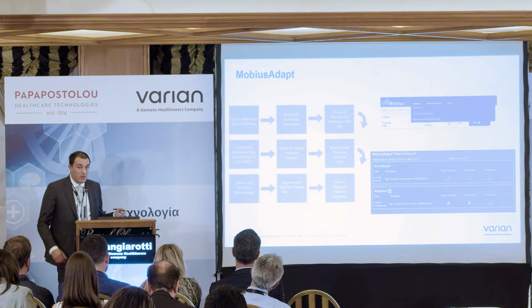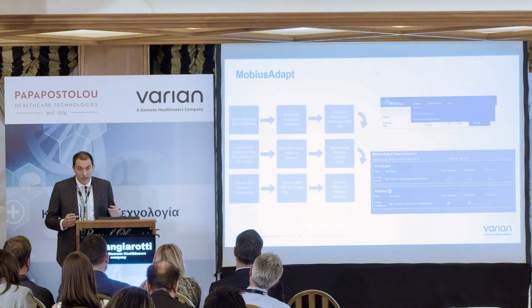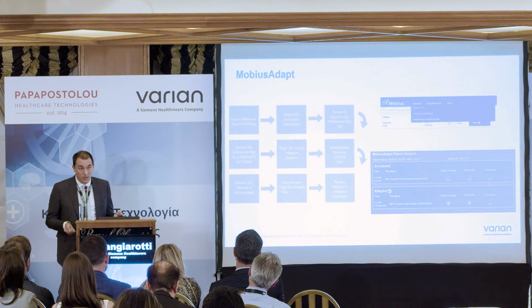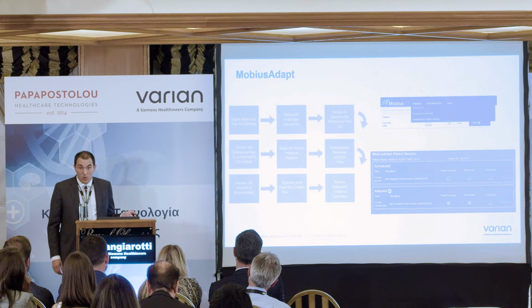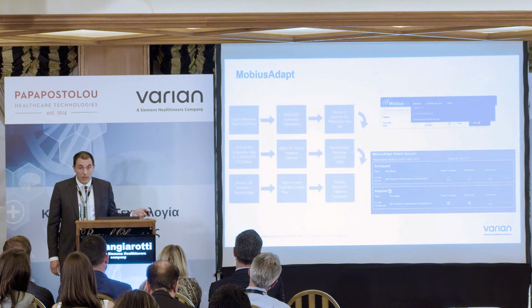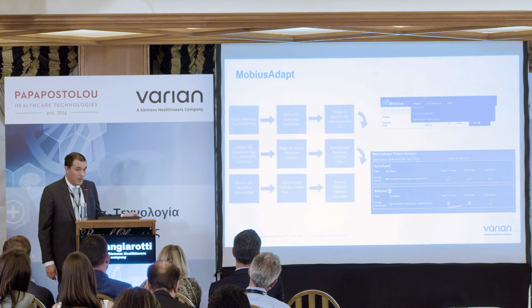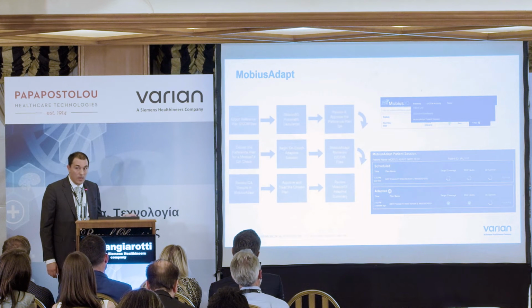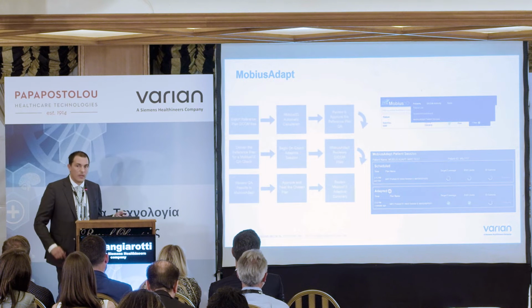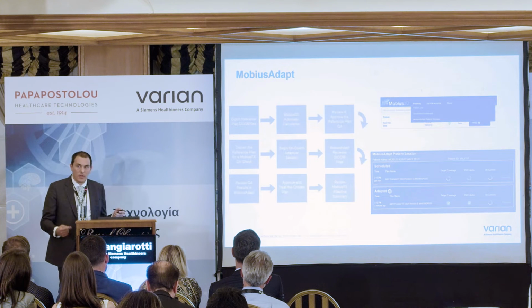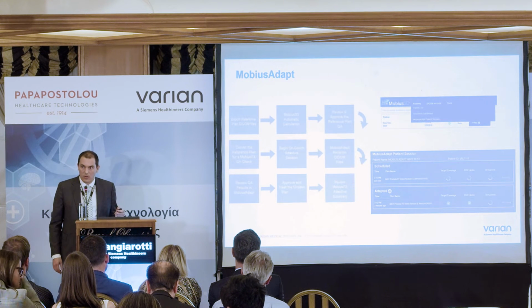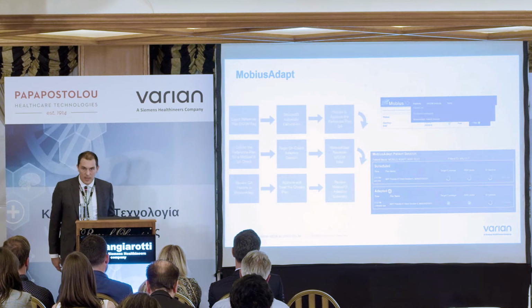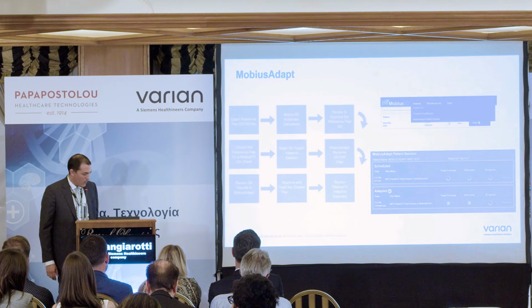When the system is re-optimizing and calculating the plan, just after the calculation is finished, the data are sent to Mobius, again automatically, so you can check in real time with the patient on the couch if the QA is passing or not. So you deliver the treatment, and after the delivery, the log files go to Mobius, and then again it starts another calculation. So you have 3 checks for every plan performed by Mobius.